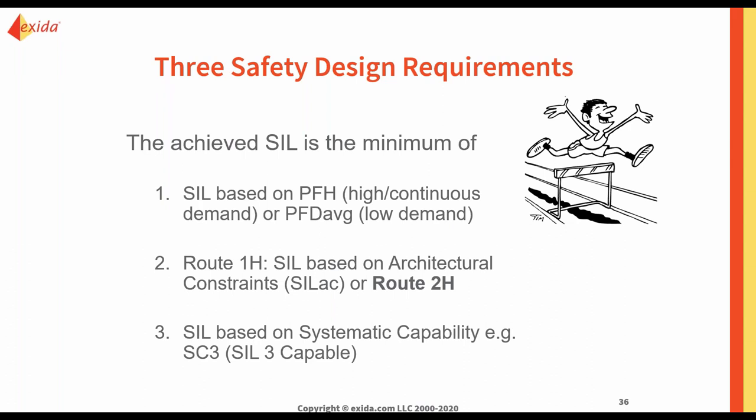But when it comes to the design of the SIF, that it needs to achieve a particular SIL, it is more than just that kind of failure, which we would call random failure. Failures that occur at random times because of the degradation mechanism within the hardware. And the PFD average and PFH would show that particular aspect. But according to the standard, you have two more points, two more pillars to look at.